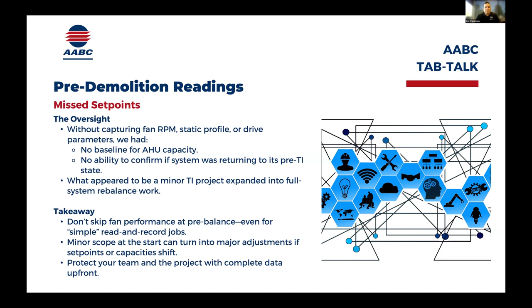Incomplete data. So this was another reference we had, talking about making sure that we go through and get everything. The scenario that I put on here was not a case of us being at fault, like we didn't grab the information. What ended up happening was they performed demo without scheduling us out there to do the pre-readings. So now we have zero baseline for the facility, and it was a pretty substantial project that went 2 floors of a hospital, and they didn't call us out there. They moved forward with demolition, got the demolition done, and realized they never did the pre-balance. Well, now they're calling us out there, and they're like, oh, can you get the pre-balance done now? It's like, you've already done demo. The system's changed. I don't know what it was. It's not like they're going to go reconnect all the ductwork and diffusers and everything else. That was already said and gone.